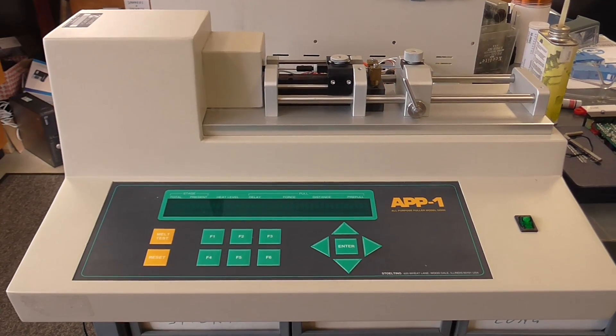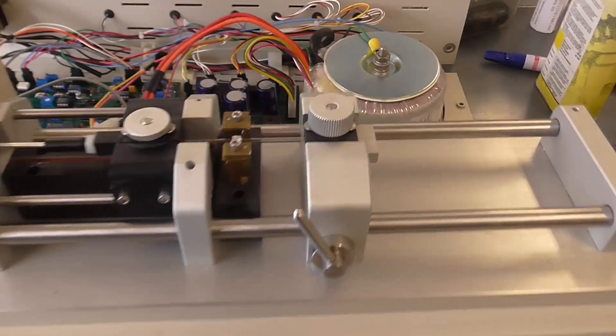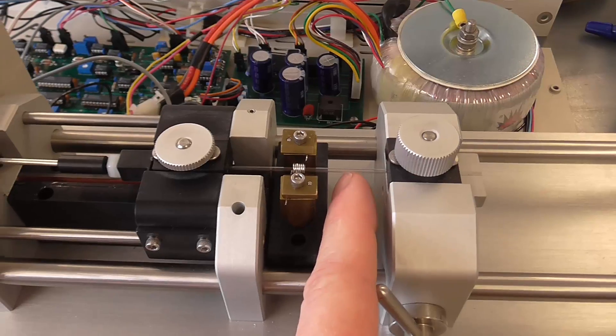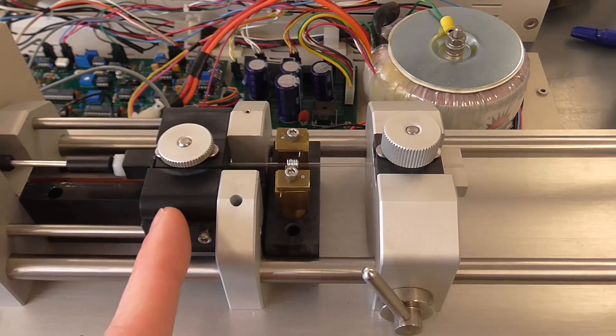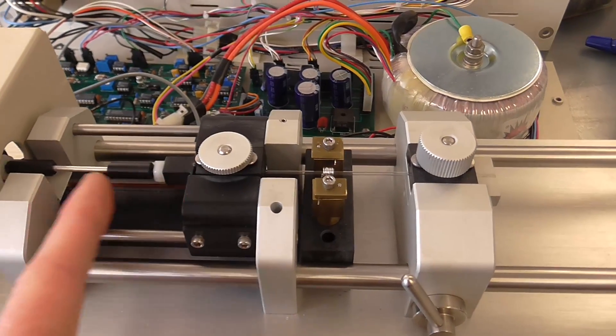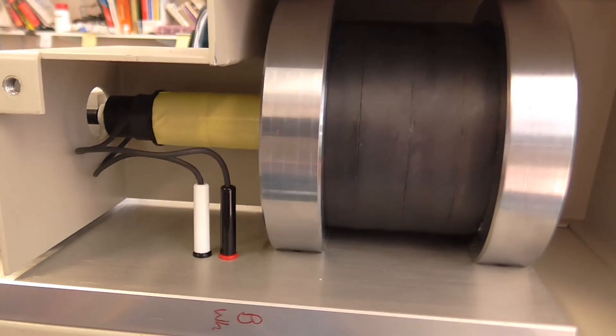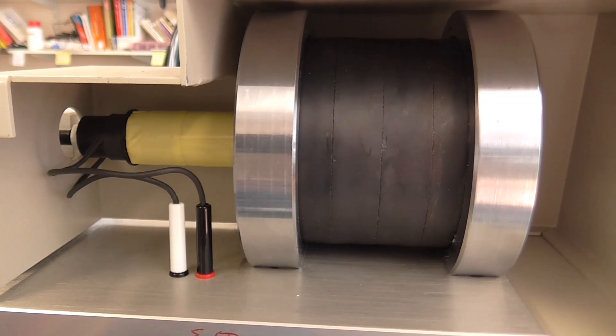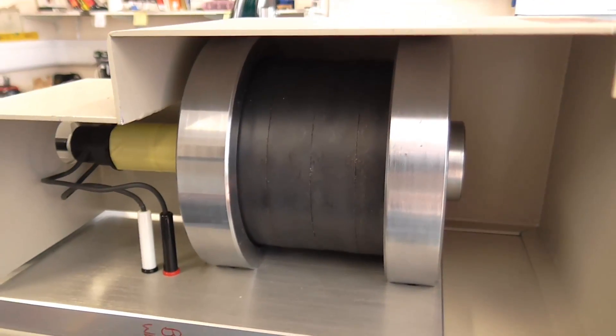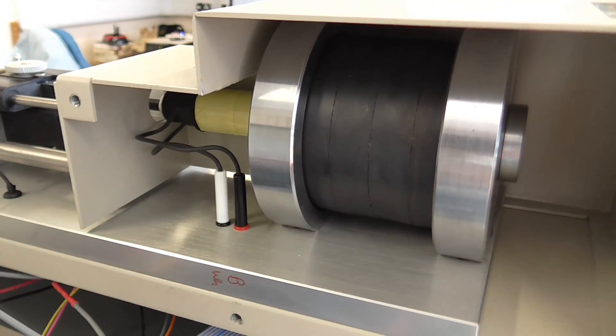This is the pipette puller I've been doing the repair on. You can see in here there's a glass capillary and a platinum heater wire, and there's the carriage with the link rod that connects to the solenoid, for which I machined and wound a new coil, a coilformer. I have run it up and it does work, and we'll run another little test in a minute.